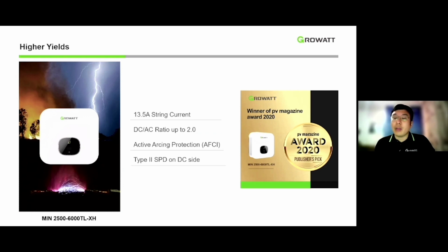Also, as long as there's a battery on site, you can get the DC to AC ratio up to 2 times. The AFCI is an optional component—if your client really cares about safety, you can add it. And on the DC side, there's also Type 2 SPD DC protection.